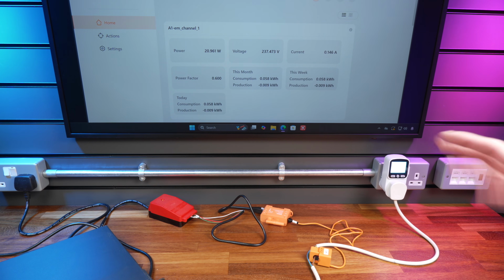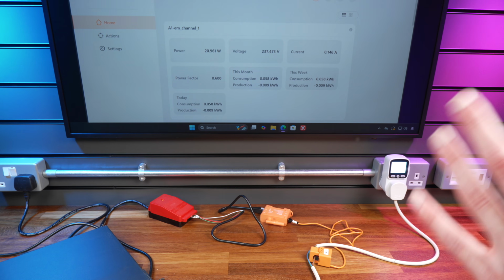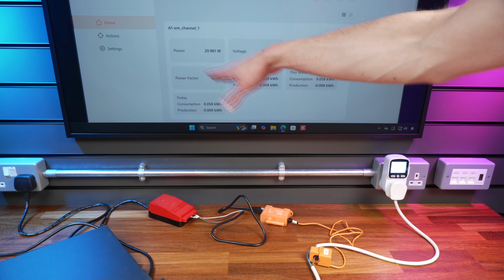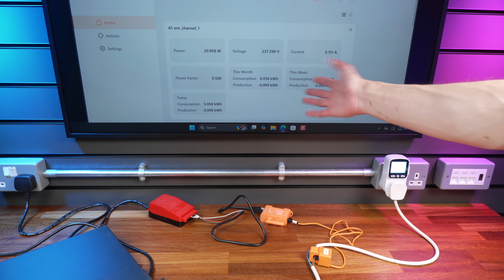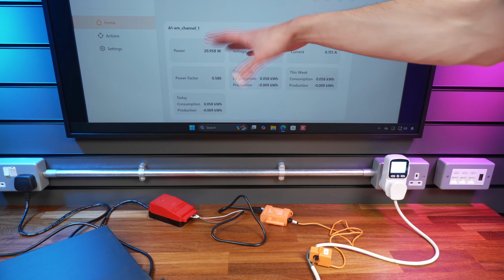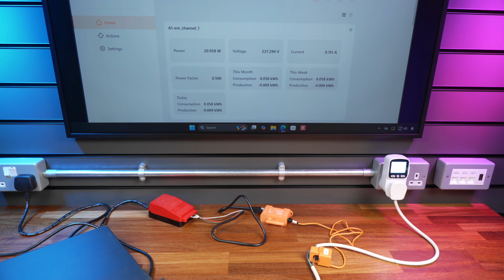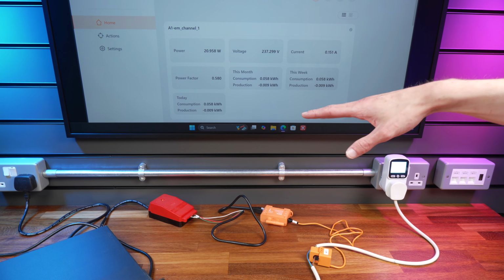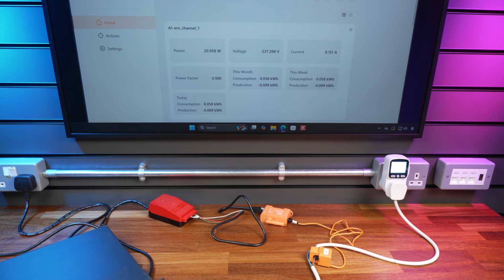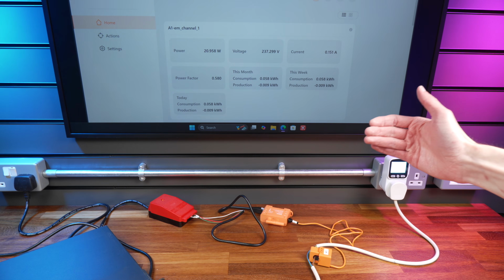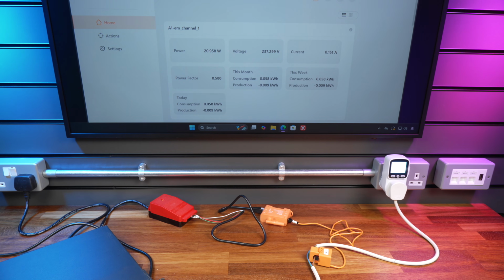So the power factor readings for my setup here seem to be a bit weird. What seems to almost be the case here is that the minimum power factor that it reports at this point, there 0.58, that's correct at that point. The minimum power factor we're getting showing up here is correct. It never seems to underreport the power factor, but it quite often spikes up to 1 or very close to 1 periodically, which is throwing all the values off.